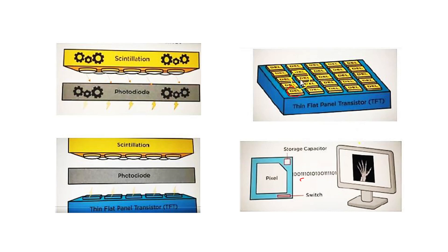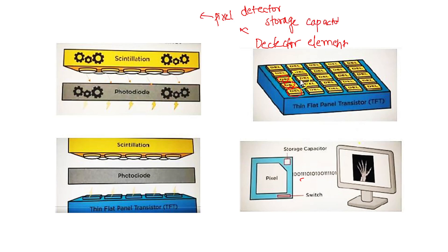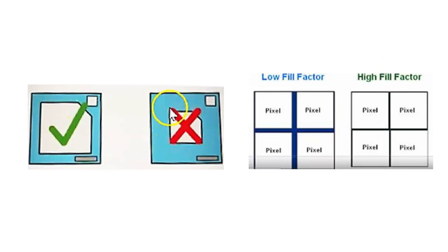The thin flat panel transistor is made up of very small detector elements, called DELs. Each detector element consists of a pixel detector and a storage capacitor. The pixel detector captures the image, while the storage capacitor stores the electric charge released from the photo diode. A switch is also present which releases the electric charge, producing the digital image. These are the three important parts of the thin film transistor in indirect digital radiography.